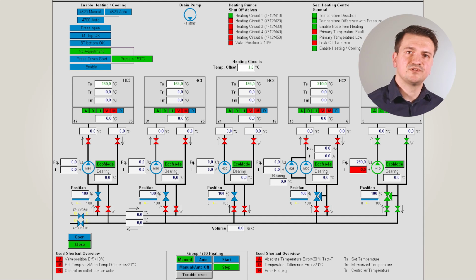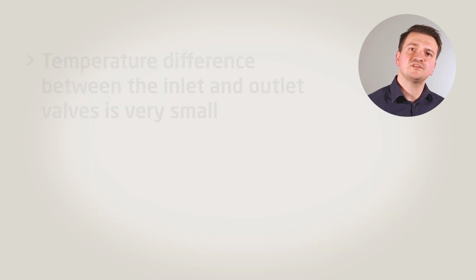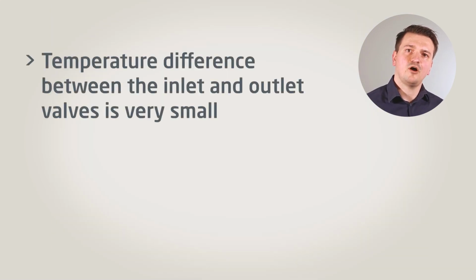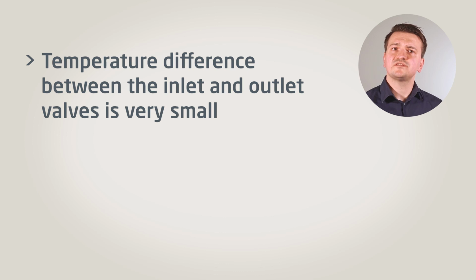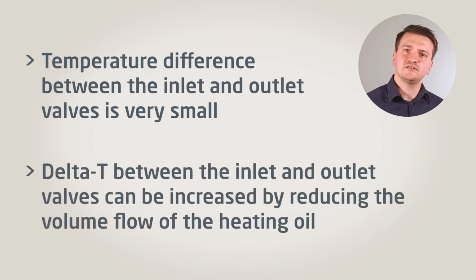The temperature difference of the volume flow between the in- and outlet valves of the heating system is very small. This in turn means the following. We can increase the temperature difference delta T between the in- and outlet valves by reducing the volume flow of the heating oil. Let's take a quick look at the physical relationship.